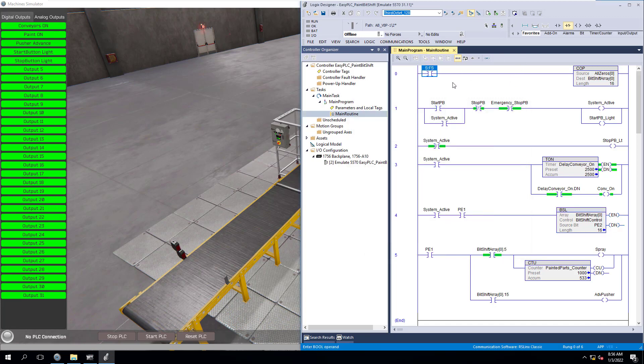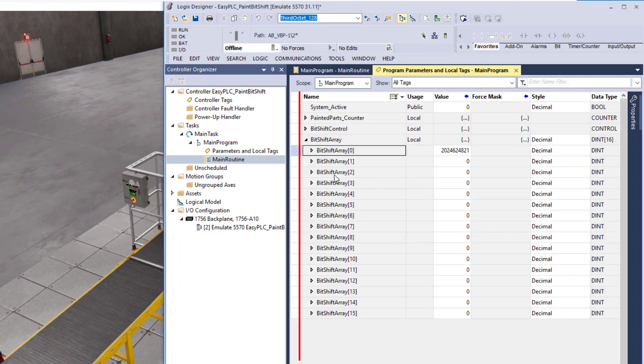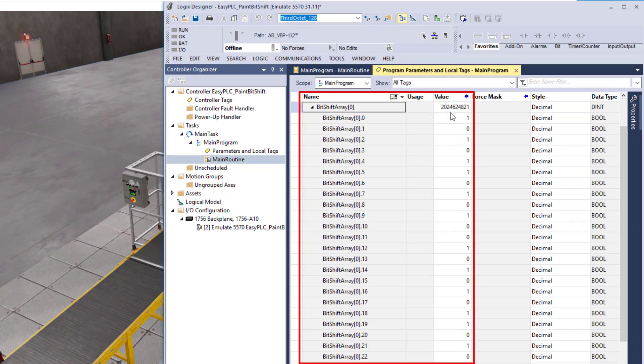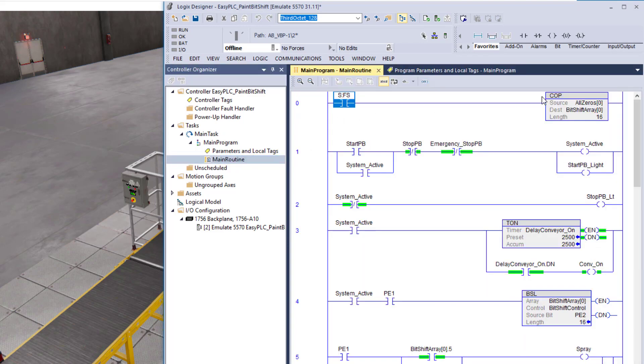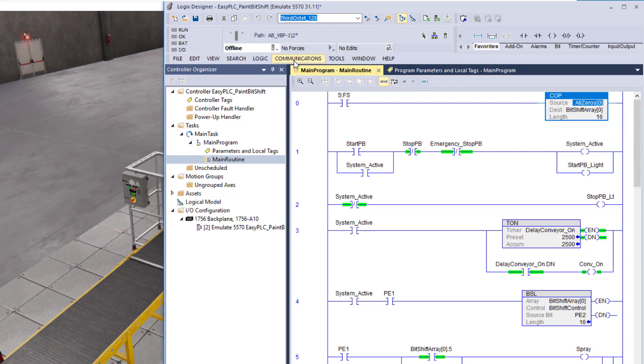Let's go ahead and download to that. First I want you to notice I have a first scan. I'm going to be writing zeros into the actual bit shift registry. Let's open up the bit shift registry — it actually has data in it. The reason I'm doing this first scan is to load in all zeros and clear the bit shift.